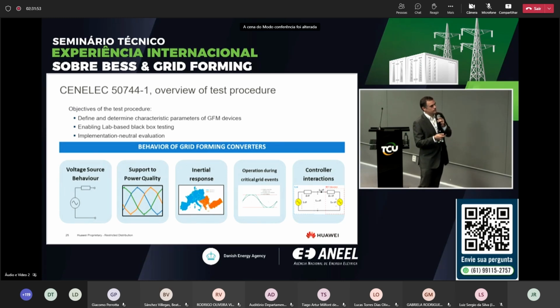I will show only this main summary here. The objective of this standard is to define and determine the characteristic parameters of grid forming devices, enabling laboratory-based black box testing, because usually for this technology the manufacturers are not showing an open box — it's always a black box because it's very new technology. It's a little bit critical. So this is considering that the black box is the only thing we have. We are going to measure according to this, with an implementation-neutral evaluation, so it's technology agnostic and so on.